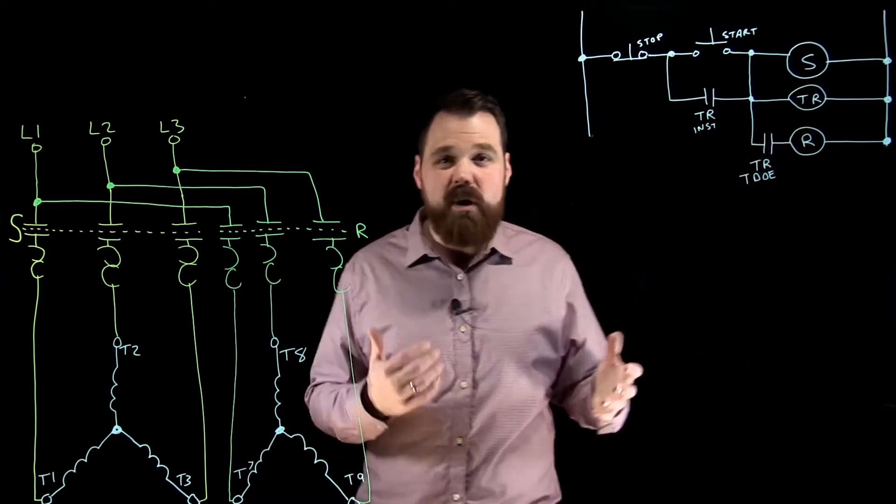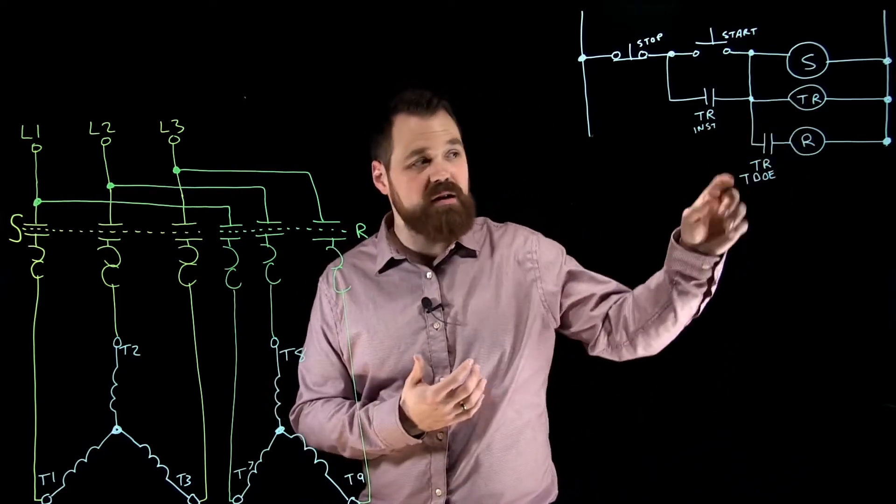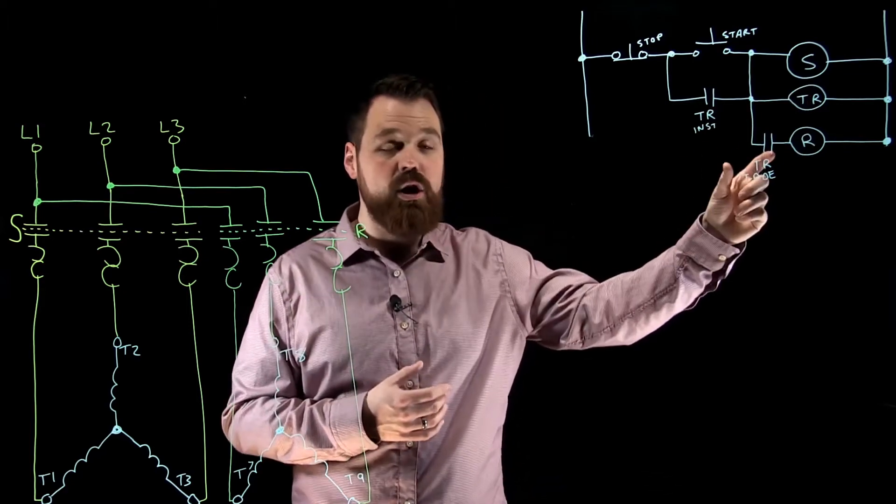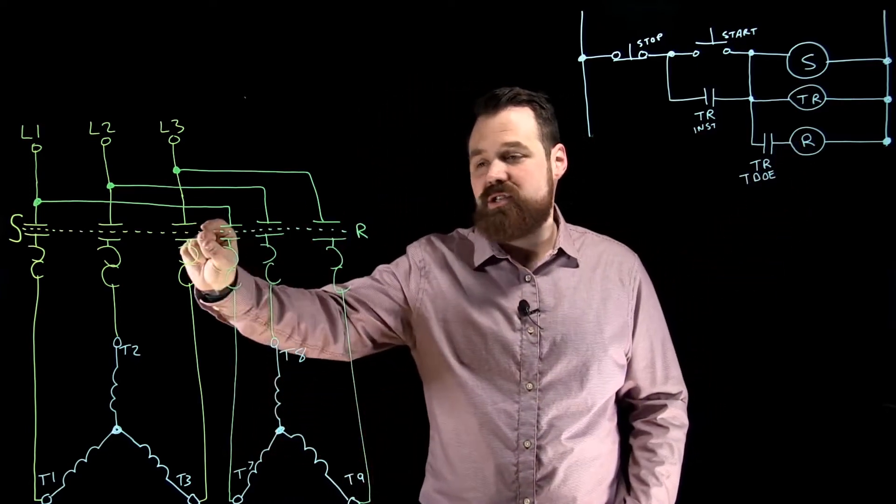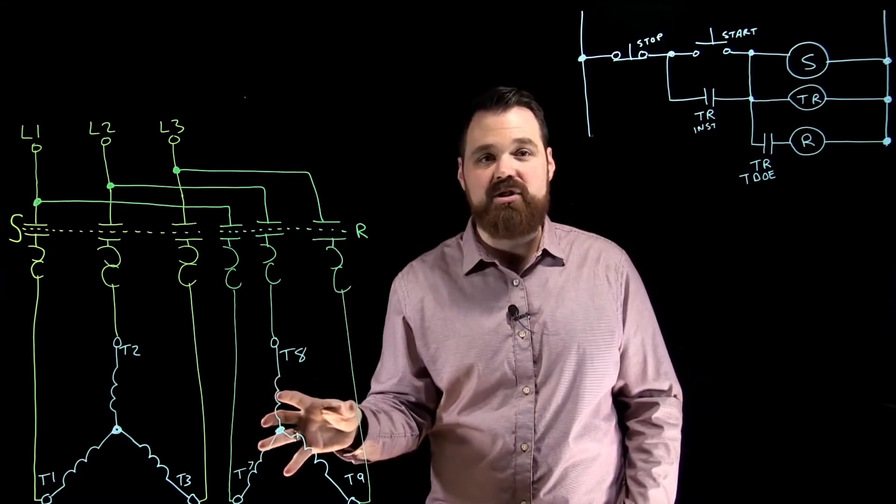After a couple seconds, usually about two seconds we see, the timing relay will finish timing and this TDOE, or time delay on energization contact, is going to close, which is going to put power to my run coil, which is going to change the state of all my run contacts, bringing my other set of windings online.